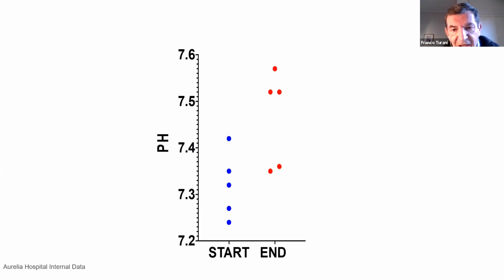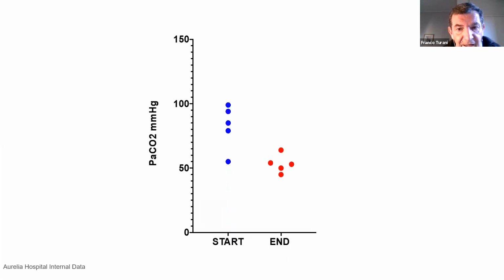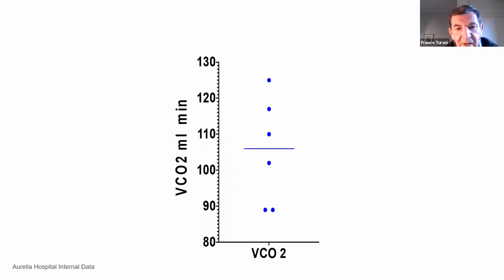We have very few data, but you see that we have an increase of pH as hypothesized by the study, and the important decrease of PCO2. We have not the data for the last patient. Interesting, the CO2 removal clearance was more than 100, was quite different. We have no statistical data from the PRISMALUNG 1, which had a little absorbing surface area. And there was a good stability for the pressure. You see all the pressure during the 24 hours of the study.